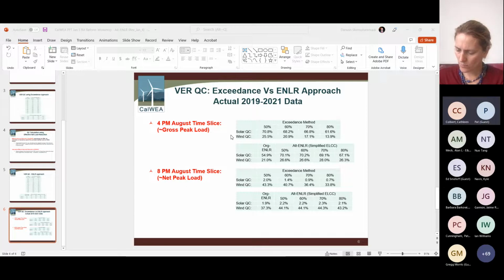Some were slices, some took this more specific approach. You could do it as an average of expected unserved energy, you could do it many different ways, but my favorite is picking the worst hour in the LOLE study for EUE and then testing to that hour. I'm not proposing it. We still think we need the workshops to refine it, but that's my favorite.